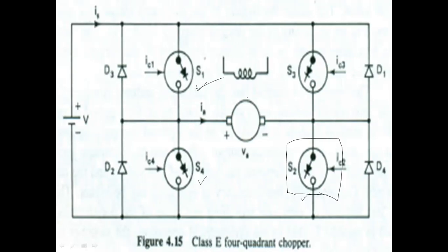Okay, the motor current reverses and it reaches the maximum permissible value then only. The current control loop restricts it from exceeding the maximum possible value. So for safety purposes, we are using the current control loop, which is used for preventing the current from exceeding the maximum permissible values.